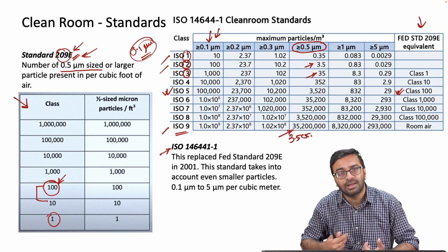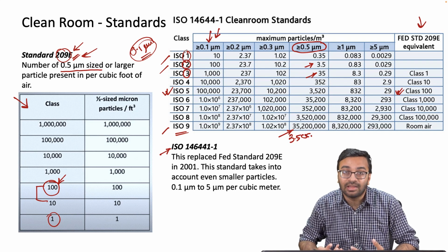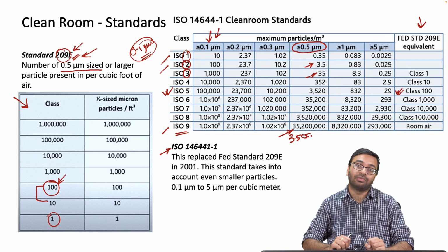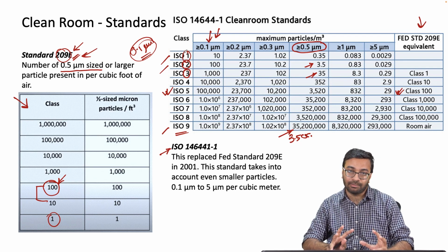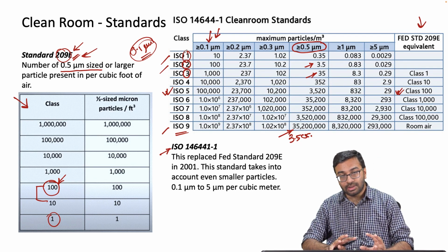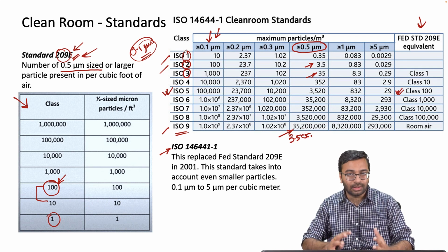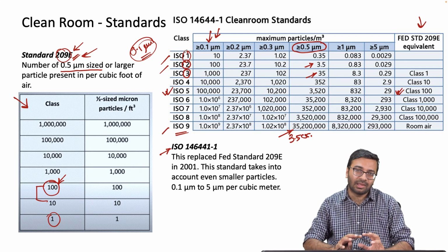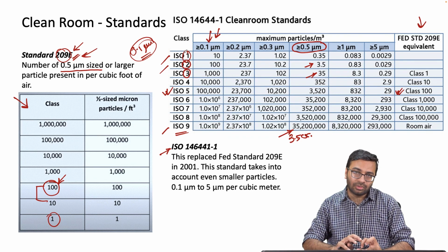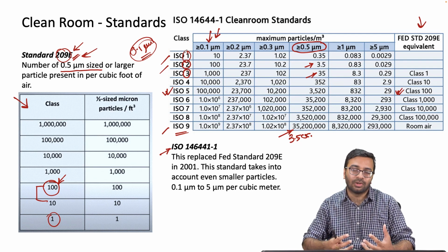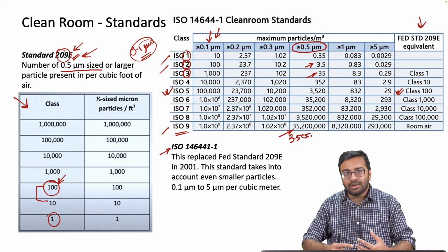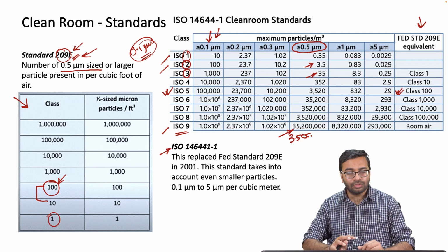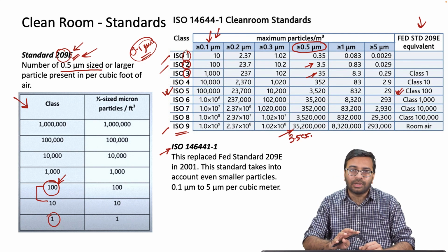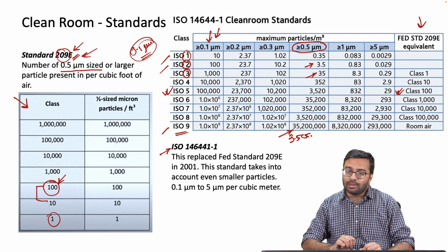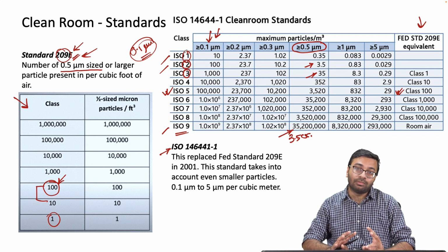However, it is expected that the cleanliness of a clean room is much higher, and the investment associated with a clean room is also very high. So it's not very easy to create a clean room setup. It may take crores of investment, 100 crores, 200 crores, say 500, 600 crores is something which I think is the investment that is required in order to create a full-fledged clean room with all the equipment. So it's not a very affordable kind of setup. One has to invest a lot in order to create a clean room, and that's why it's very important that you maintain that clean room properly.